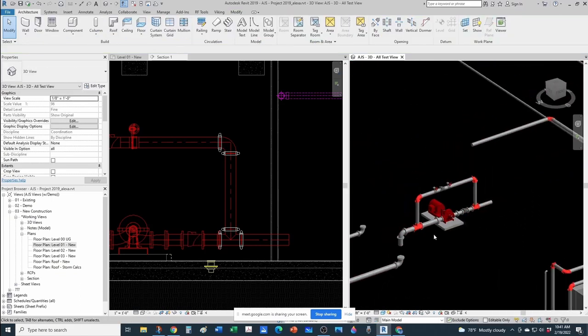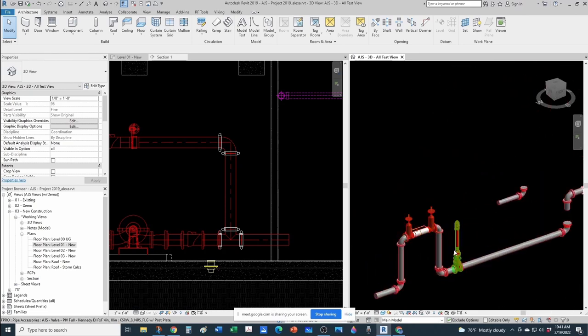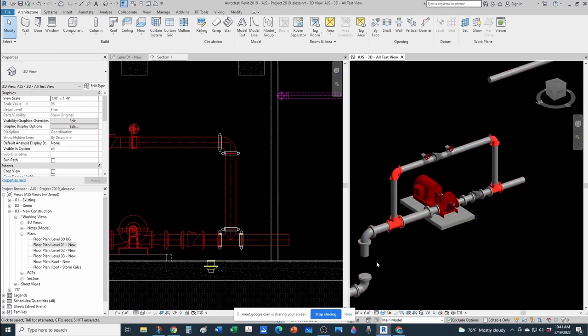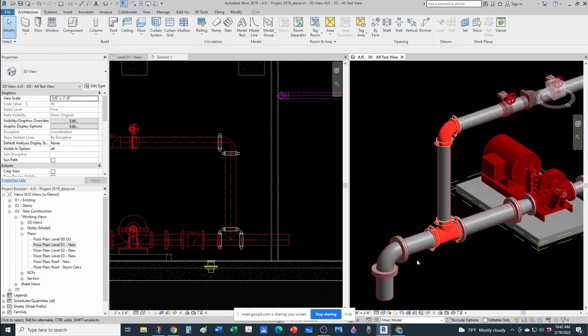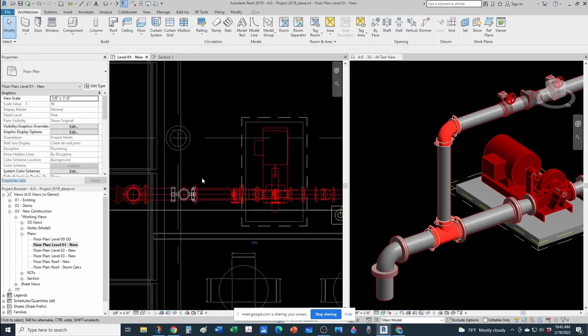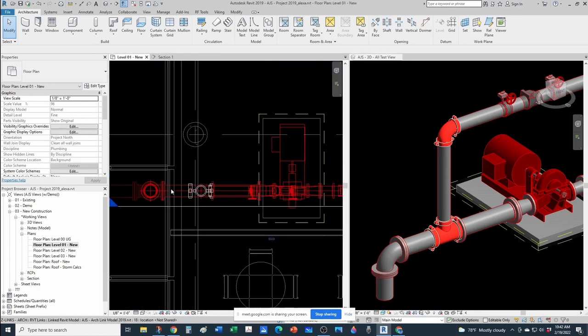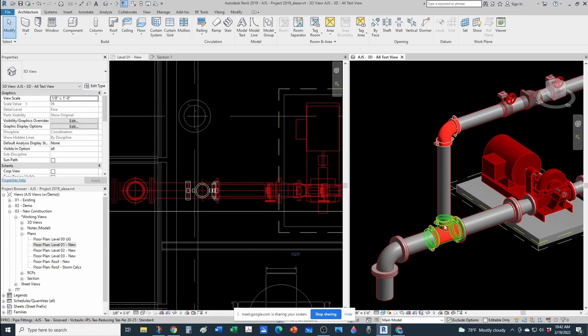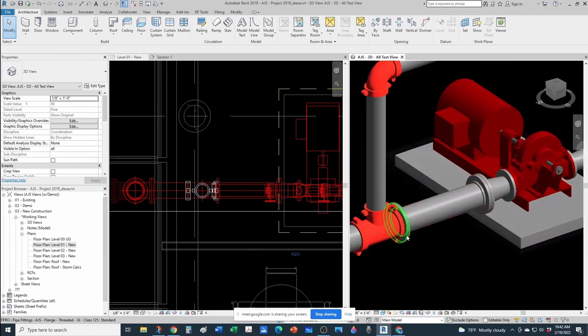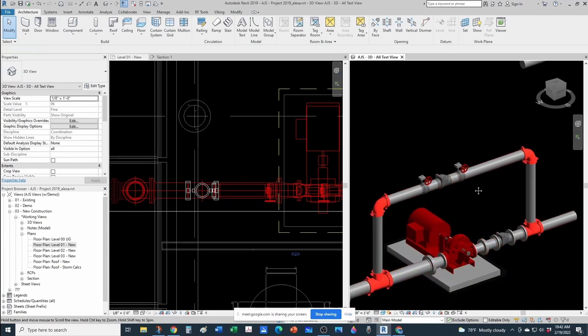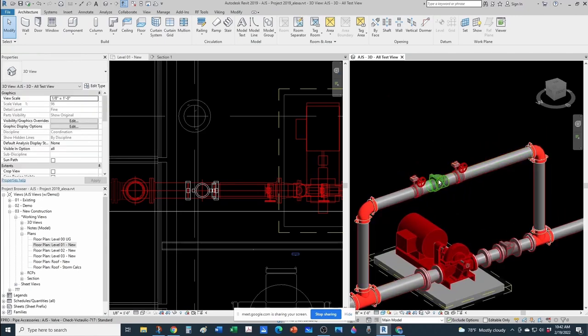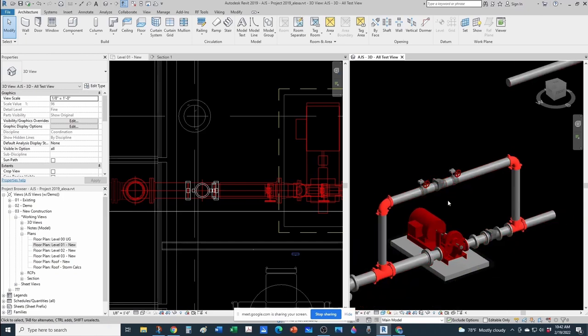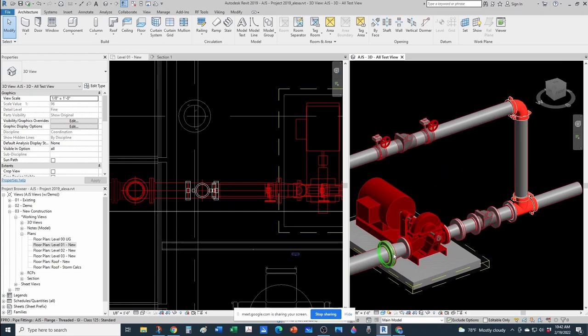A quick summary of where we're at right now for those who just joined. That's our backflow preventer, post indicator valve. This is our suction line. That's our flange elbow to the entrance of the building. So if you see, the wall for the building would be this one right here. Then we can transition into groove fittings. This is our bypass here, which needs to have a check valve and two isolation valves to provide some maintenance to that check valve whenever required. Then we need that reducer. This is an eccentric reducer, to prevent air pockets.